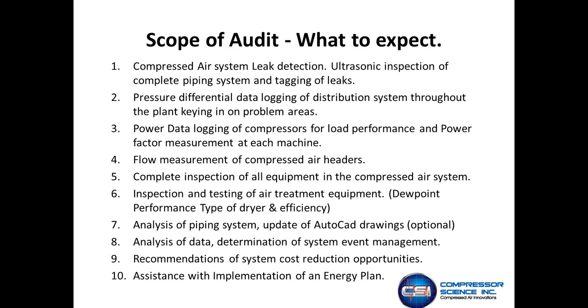Data logging, of course, of the compressors for load performance, and power factor measurement at each machine. Power factor measurement is critical because if you're taking amperage measurements and voltage measurements, you really need to know the power factor to correlate correctly into kilowatt consumption.